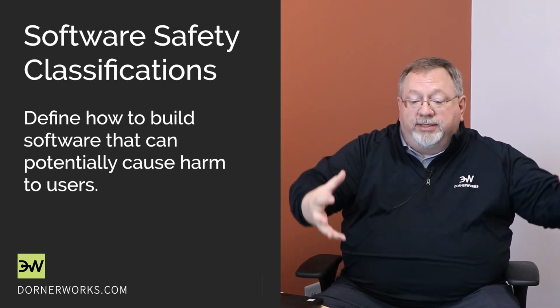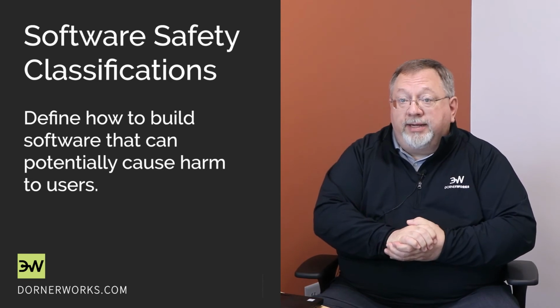All of this bundles together: the requirements, the risk analysis, the software design, the code, the test cases and test results all get bundled together into a software design file that is delivered with the product. And that software design file then defines the artifacts that are analyzed by the FDA to verify that the software is in fact compliant with its design internally and with FDA rules.